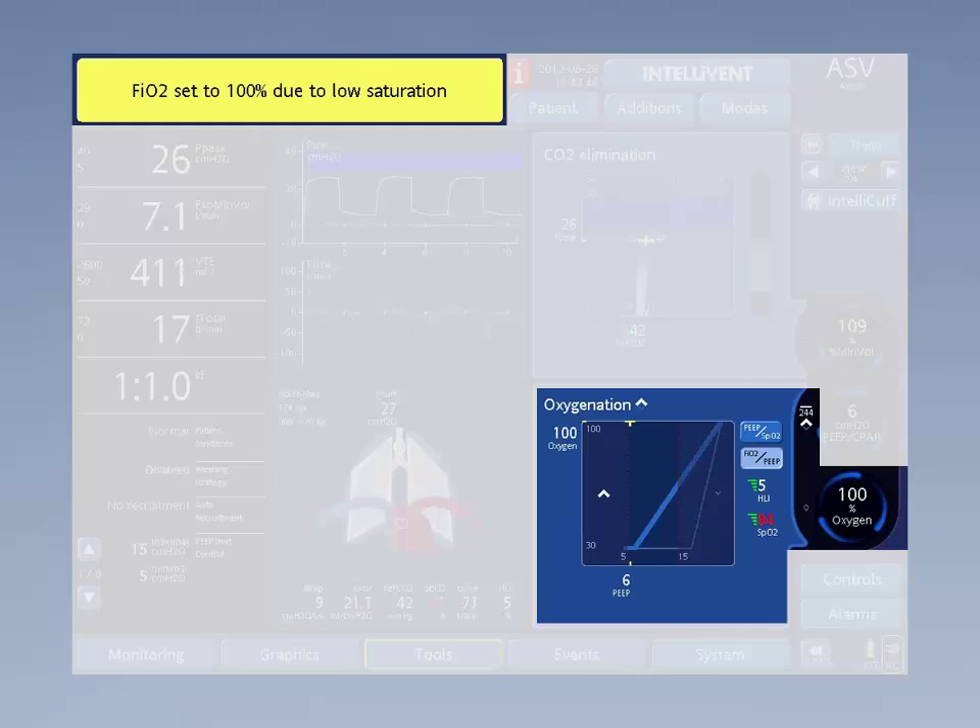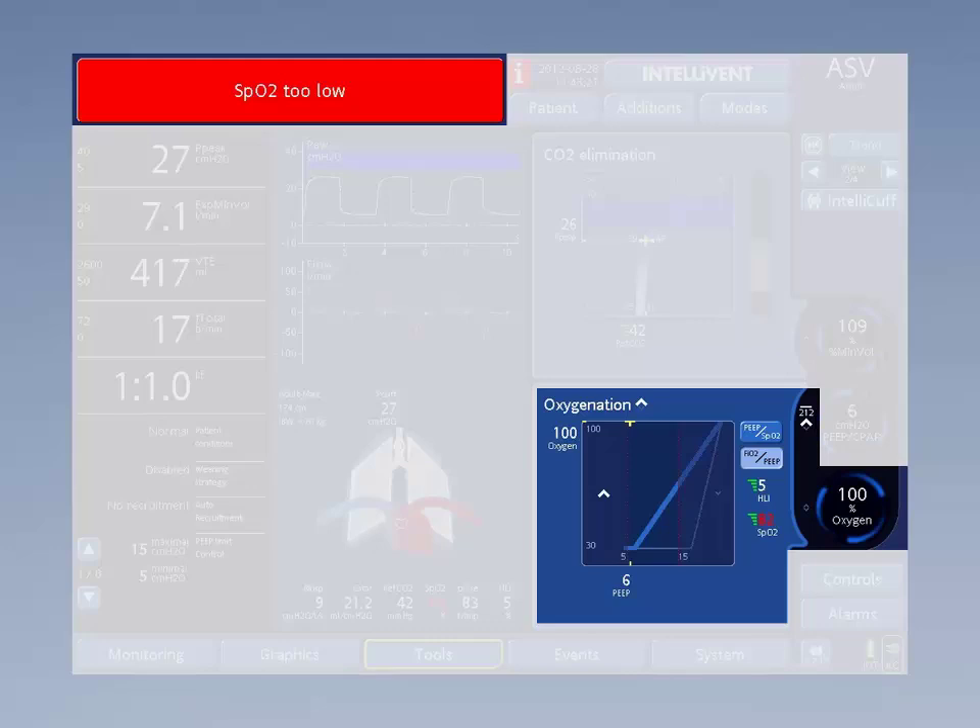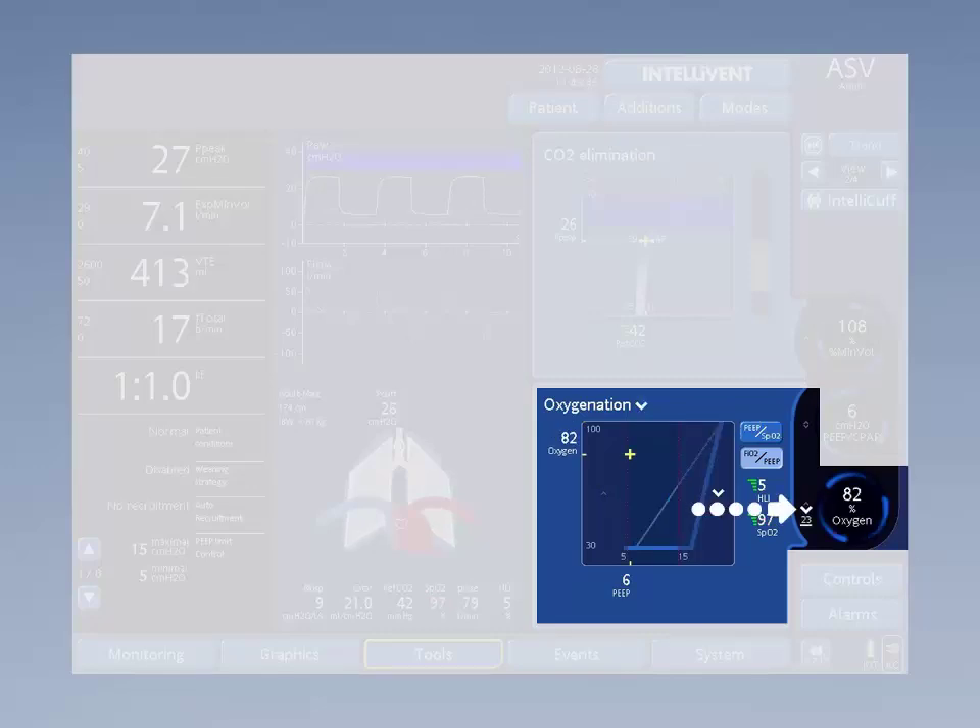When saturation drops dramatically, the SpO2 will enter the dark blue zone and the safety algorithm of IntelliVent ASV will set the FiO2 to 100% and give a high priority alarm. Any increase or decrease in therapy is visible through the arrows next to the controllers and the timers. The timers provide a clear overview of when events will happen. Overall, the oxygenation and ventilation controllers function according to currently used guidelines to support physicians in their daily work.